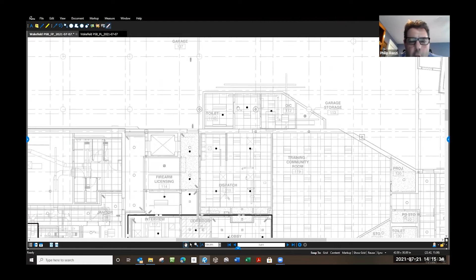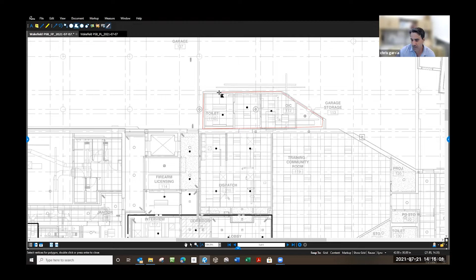You mean this area where the toilet is, that's all open, caged in, open to the garage? I don't know, is it a dry system in the garage now? It is currently. So I would guess I don't know if there's coverage in there, or maybe there's nothing—it doesn't exist now, so I just bring that up as something to be mindful of. Yeah, it is a protected area, but I think the thing to do would be to take that off of the existing dry system and feed it back from the wet. That would make the most sense, so we'll convert that to the wet system.